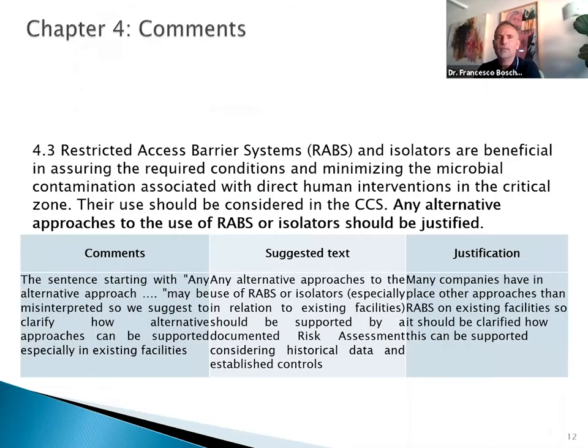By EIPG, we issued a comment, for example, at point 4.3, specifically related to the part where the annex states that any alternative approaches to the use of RABS and isolators should be justified. Our comment was that the sentence starting with 'any alternative approach' may be misinterpreted. So we suggest clarifying how alternative approaches can be supported, especially in existing facilities, because many companies have conventional clean rooms in place right now, so it should be clarified how this can be supported, at least for the short term.